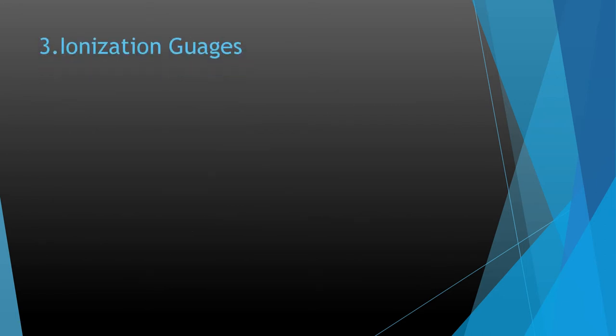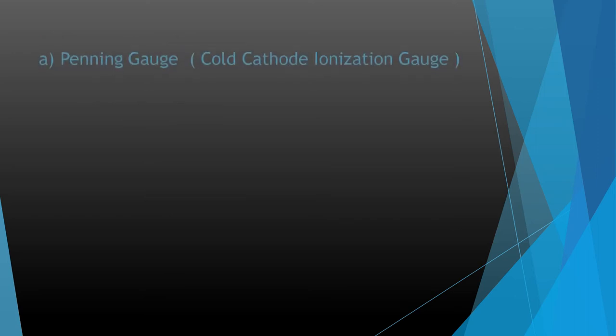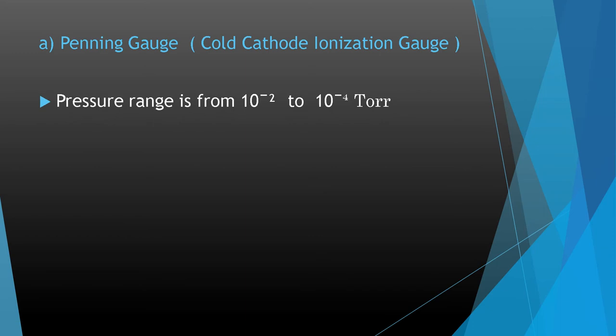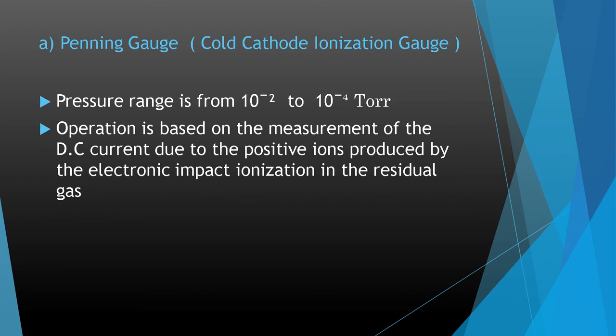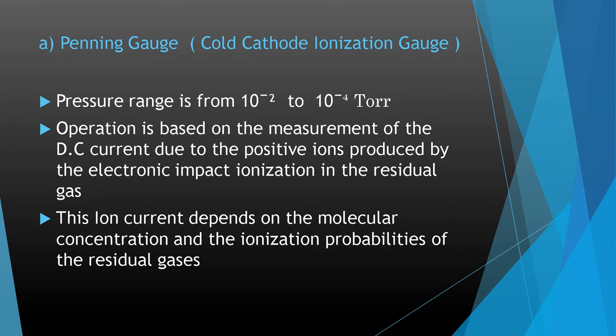The next type is ionization gauges, which are of two types: the cold cathode type and the hot cathode type. The cold cathode ionization gauge is also known as the Penning gauge. Its pressure range is from 10⁻² to 10⁻⁴ Torr. The operation is based on the measurement of DC current due to positive ions produced by electron-impact ionization in the residual gas. This ion current depends on the molecular concentration and the ionization probabilities of the residual gases.